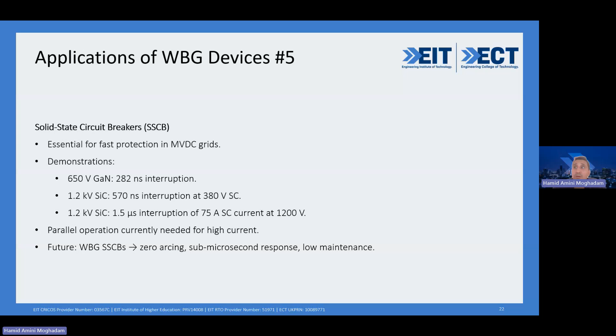Another example showed 1.5 microsecond interruption for a 75 amp short circuit, with a voltage of 1200. If you want to go to higher currents, you can usually parallel these things together to achieve higher current. The future is wide bandgap solid state circuit breaker, because firstly it doesn't have any arcing. As I mentioned, traditional circuit breakers will have arcing because it's physical, right? It is literally a contact. And so when you separate at high voltage, imagine that 1200 volt, it will arc. But because we are talking about wide bandgap devices, there is no arcing, right? Because there is no physical contact. We are talking about sub-microsecond response and also low maintenance, which is very important.